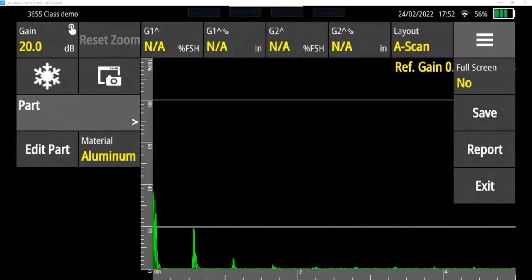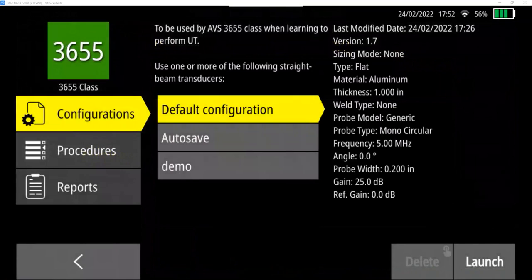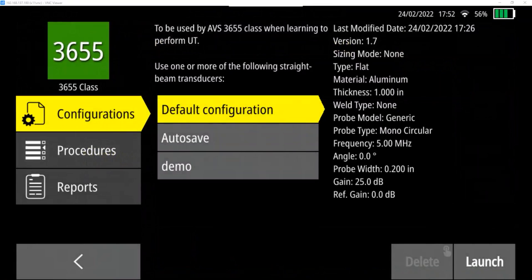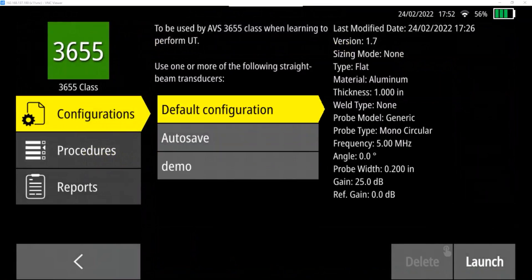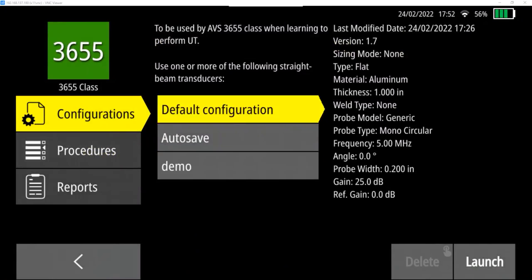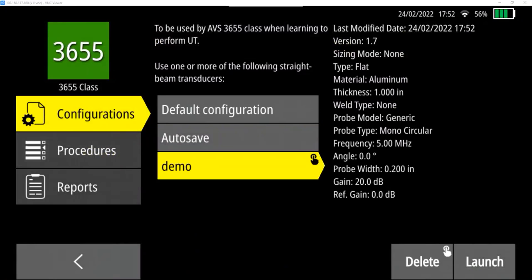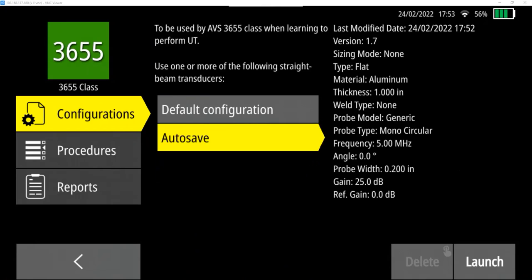And then finally, if I want to leave this screen, if I want to leave this testing configuration, I can press exit. And now you can see exit has brought us back to the configuration select screen. And now there is the demo configuration that I saved. And the difference – so default configuration, the one I'll point out is gain on the right side over in this area. It was originally 25 decibels. And in our demo, I had changed it to 20 decibels. So now it shows those. If I want to go back into there, I can press launch. If I'm not going to use it, I can press and hold delete. And you'll see that one has now gone away.